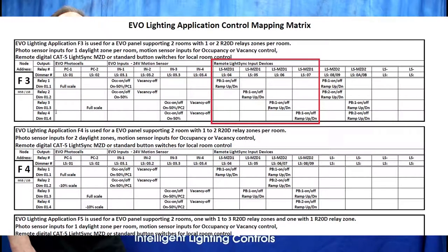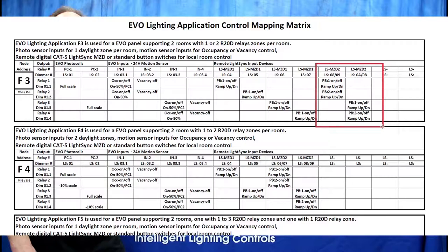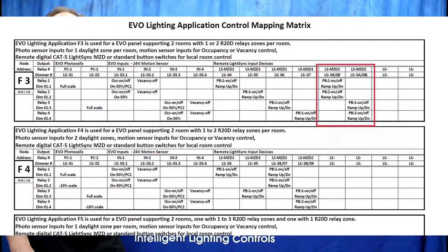From the matrix I see that light sync digital switch address 08 is for an MZD station that will control relays 1 and 2, and address 0A is for an MZD station that will control relays 3 and 4 for the second room. Keep in mind that an MZD 2, 3, and 4 zone device uses two light sync addresses. You set the switch for the first address and the second address is automatically mapped — the device still uses both addresses.